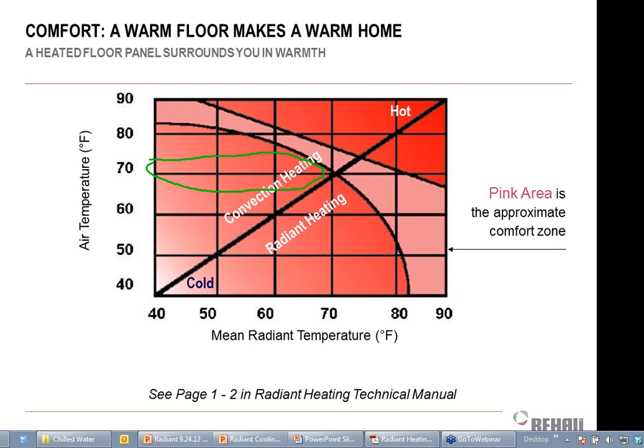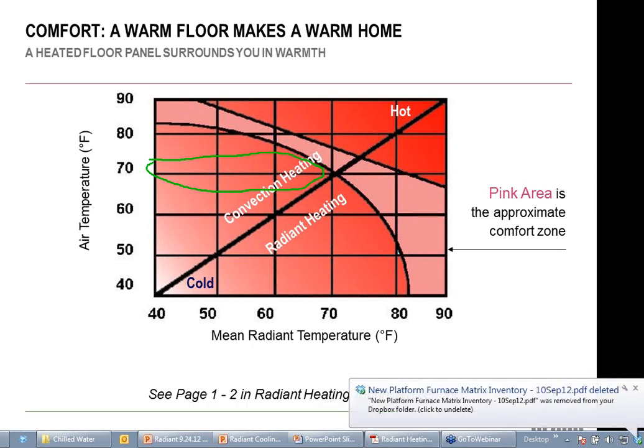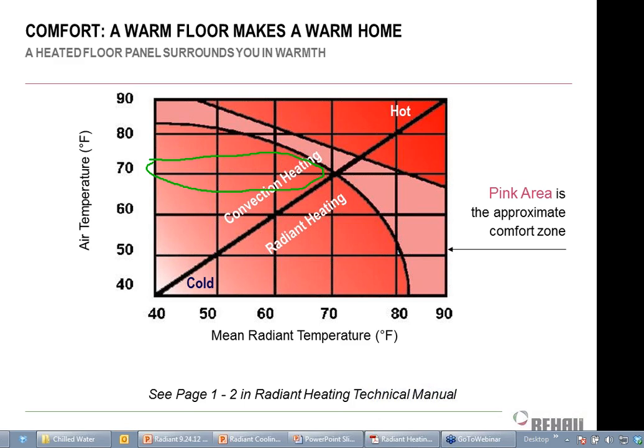Whereas with a radiant system, I have very little control, at least directly, over the air temperature. I'm controlling the radiant temperature in the space, so I'm having control over things below this black line over here. I'm still going to have the air temperature be fairly warm, but I'm probably going to have it a little bit cooler. I'm probably going to be operating primarily in this range, right? So a little bit cooler air temperature, but I have control over what's going on radiant-wise.